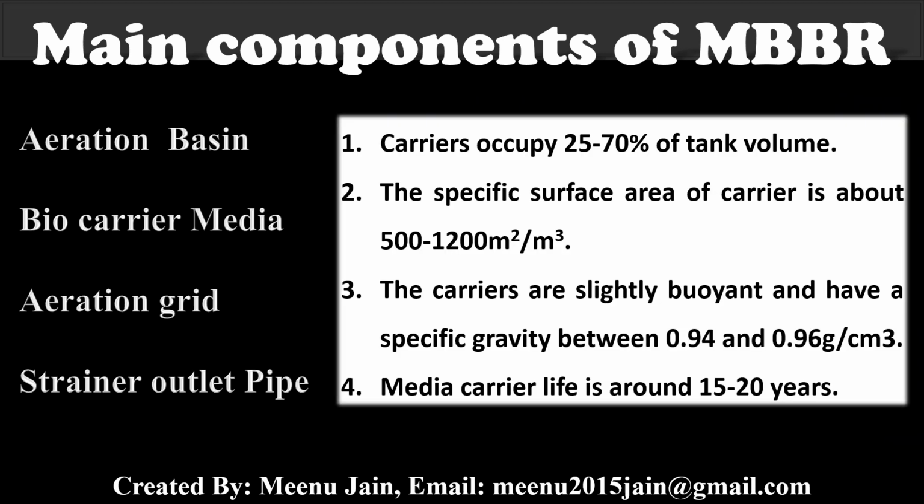Here, there are some key points of MBBR carrier media. First, the carrier occupies 25 to 70% of tank volume. Second, the specific surface area of the carrier is about 500 square meters per cubic meter to 1200 square meters per cubic meter. Third, the carriers are slightly buoyant and have a specific gravity between 0.94 to 0.96 gram per cubic centimeter. And fourth, the media carrier life is around 15 to 20 years.